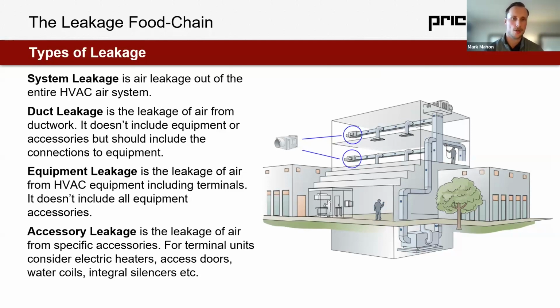In my case and in my scope, we'll look at terminals here. And interestingly, it actually doesn't include necessarily equipment accessories at all. So the last leakage here, which we'll also talk about, is accessory leakage. And that's the leakage from a specific accessory or appurtenance. So is it an electric heater? Is it an access door? Are we looking at water coils and the slip and drive seams on water coils, or potentially an integral attenuator or silencer, or a duct mounted attenuator or silencer? That's accessory leakage, and that, once again, is separate and managed separately.